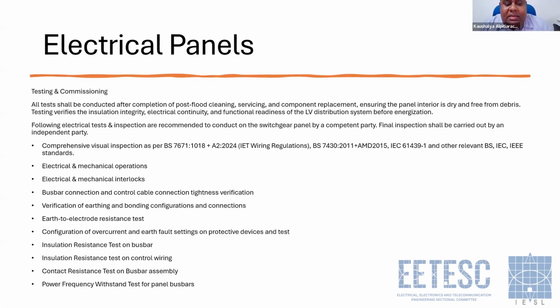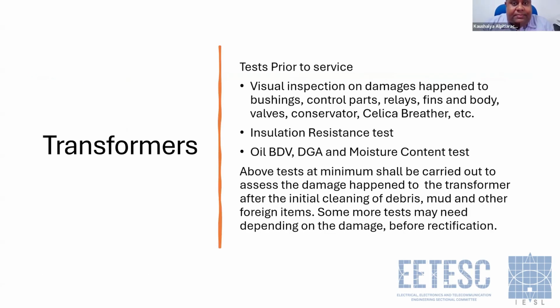Insulation resistance test on bus bars, insulation resistance test on control wiring, and contact resistance test to check whether you are developing hotspots at your connections and terminations. Then a power frequency voltage withstand test for panels, bus bars, and circuit breakers as well.